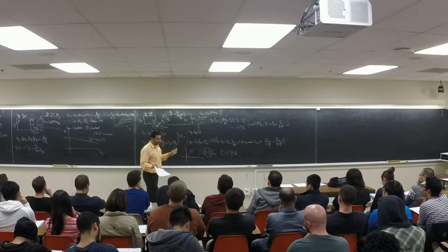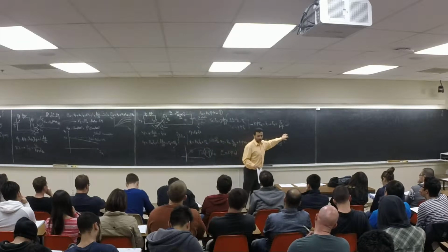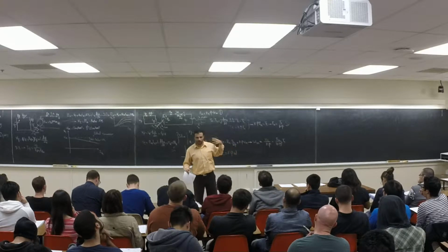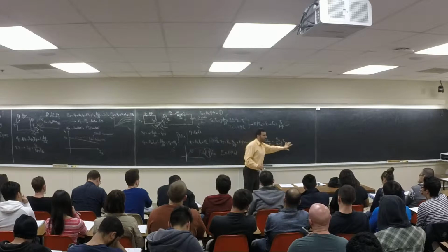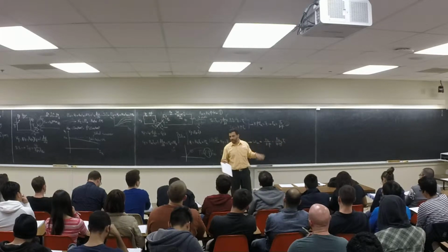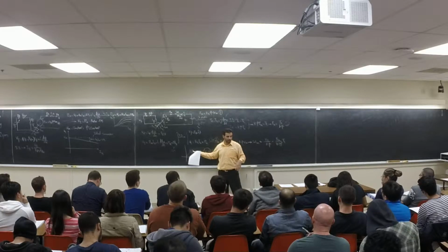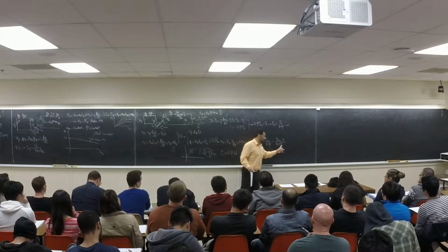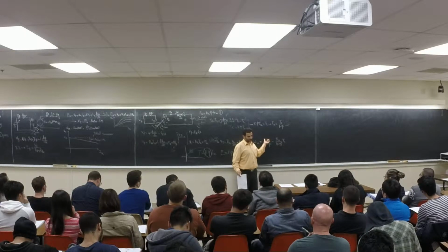But just to make it simple, there is a voltage control, flux control, armature control. Armature control is not good because it's going to add more resistance to the circuit. It's going to cause more loss in the circuit. Efficiency drops. Flux control in general is not good because, first of all, we would like to work with the best flux possible, maximum flux possible to get the best torque performance. And the second, the control is nonlinear, right? So this one is the best.